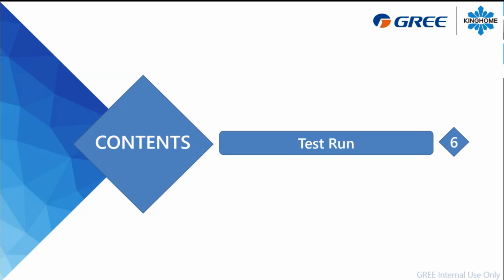It will consume maybe 3 amps. It's very low. But when you install, for example, a 5 kilowatt duct heater, the 5 kilowatt will take like 20 amps to run, plus the blower, the board, and all the stuff. So you need a 30 amp breaker just to run a 5 kilowatt duct heater. If you go to a 10, you need to add 20 more amps. So it's 50, but that's really a little bit too close, so you will go to a 60 amp breaker for a 10 kilowatt. And you add on and on like this.